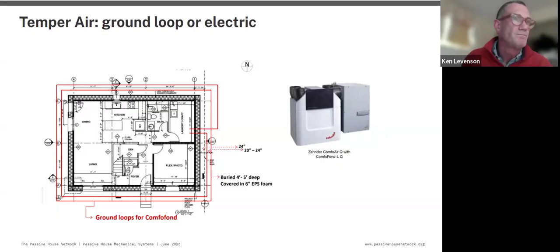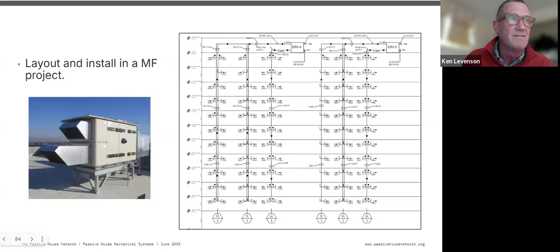Centralized systems. So another kind of animal, perhaps, but all the same principles. The big thing, we're typically going to have big units either on the roof or on a lower roof or next to the building or in interior space, but often on the roofs. You've got these big risers and long duct runs. Passive House does not require you to test the duct leakage. But it recommends that there be no more than 2% leakage maximum because we need to make sure that air is getting to where it needs to be.